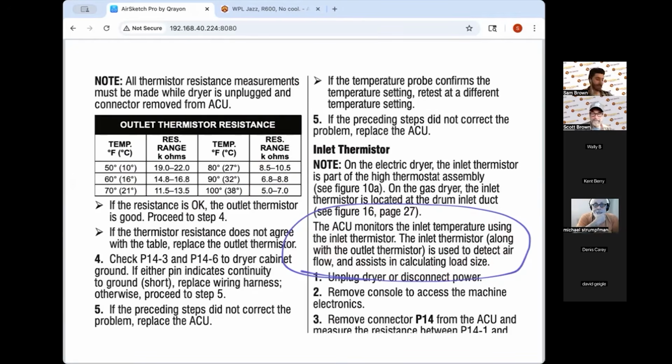If there are specs you need, like a thermistor table, that are just missing from where you think they should be, that's your cue to start pouring through all the information you have until you find them. Because they're there somewhere, and if they're not, then that's where your troubleshooting stops. It's not like the old days where you got a paper manual and you had to thumb through and read each one. It's a PDF. Pull it up in a PDF reader, use the find function, and search for keywords like thermistor. It'll just take you minutes to get right to the page. Oh, look, this one has it out of the 12 possible pages with the word thermistor on it. Then you just thumb through those find results real quick and there you go.